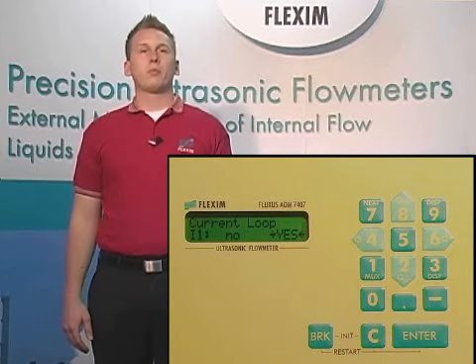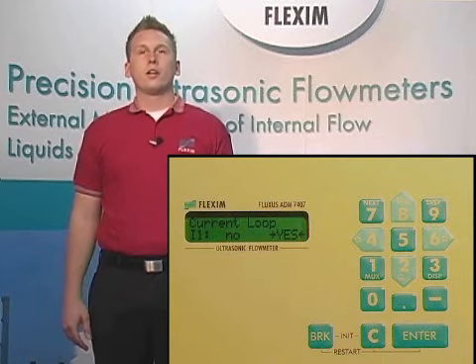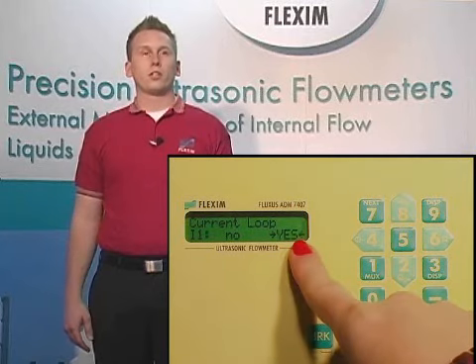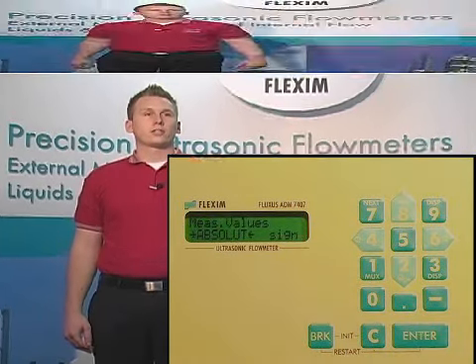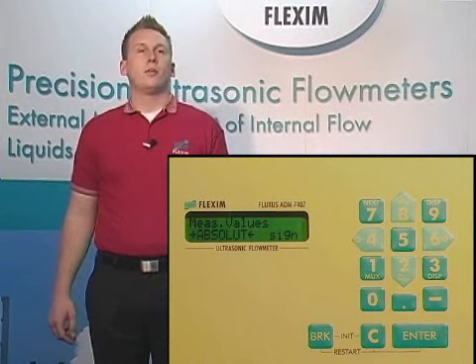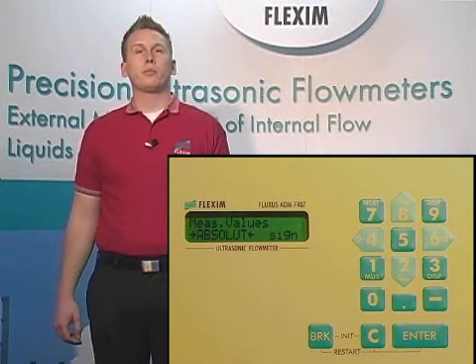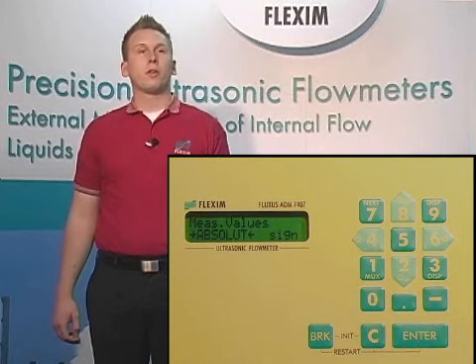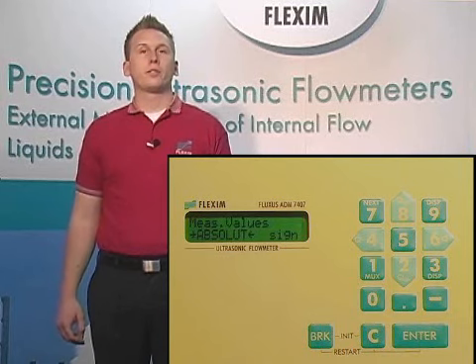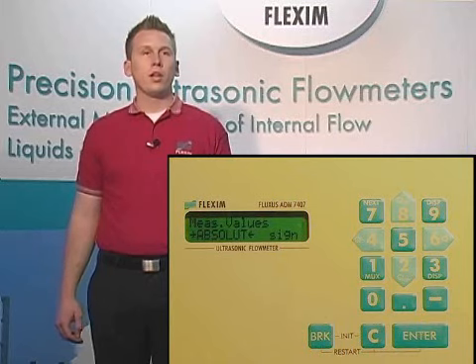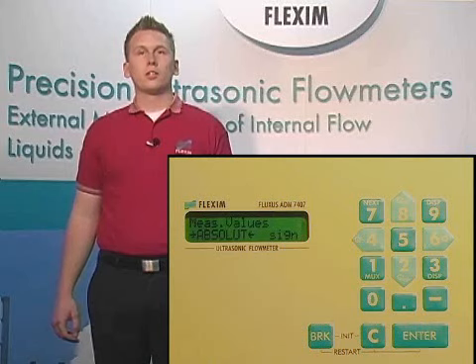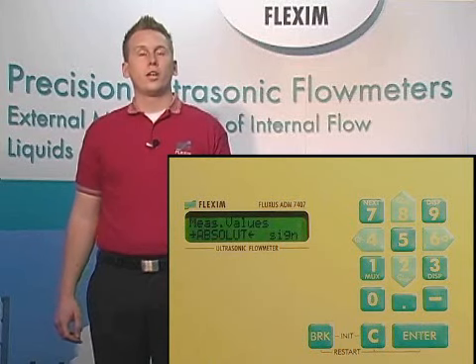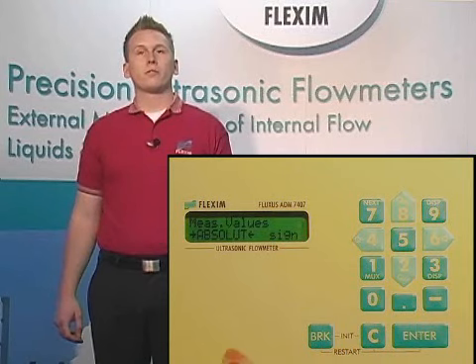Now, we're prompted whether we'd like to use the current loop or not. This is how we enable and span our 4 to 20. Let's choose yes. Next, we're asked if we want our measured option to be an absolute value or signed, meaning whether we want to show flow as a negative if it's flowing in the opposite direction we think we're flowing. This option is entirely preference, but I'm going to choose absolute. This way I don't have to span my 4 to 20 from negative max flow to positive max flow. This will ultimately give us better resolution for our output.